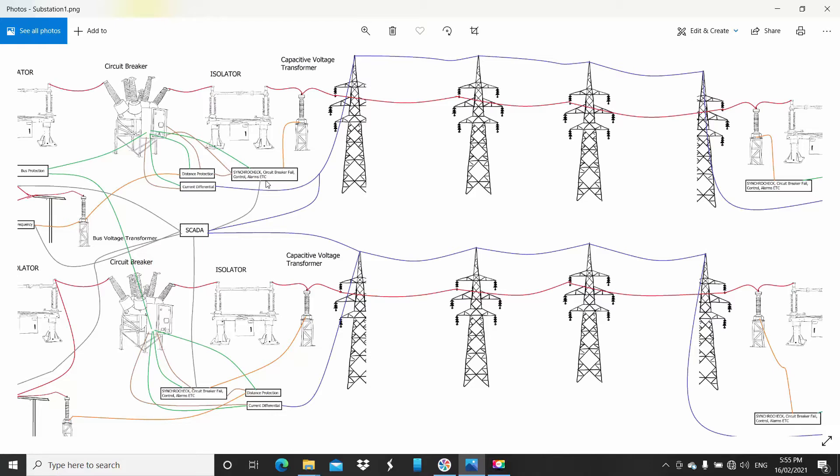And a different position of the voltage vectors. You want to make sure they're the same when it closes on, then you can synchronize the network. Back in the old days, they used to have a synchronization meter and watch it move and wait for the two sources to be the same, then close on. That's the idea behind that.